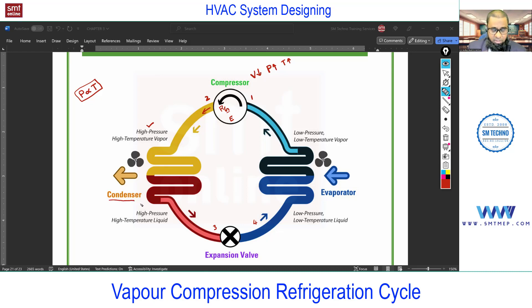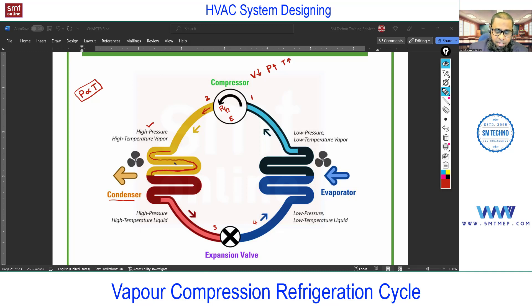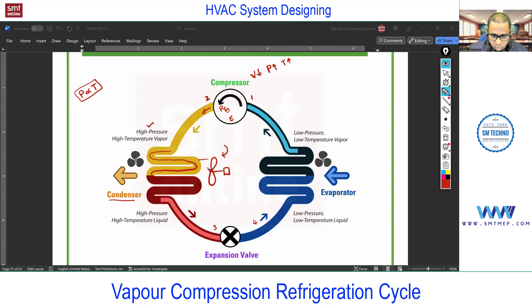The name 'condenser' gives you the idea — condensation happens inside, meaning a change of phase from vapor to liquid. The refrigerant enters the condenser as vapor with high pressure and temperature. It flows inside the tubes of this heat exchanger, so heat exchanges from this refrigerant to outside. This heat exchange can be done by supplying air — for example, using a fan to suck air from outside and throw it onto the coil. The outside temperature compared to the refrigerant temperature should be less.